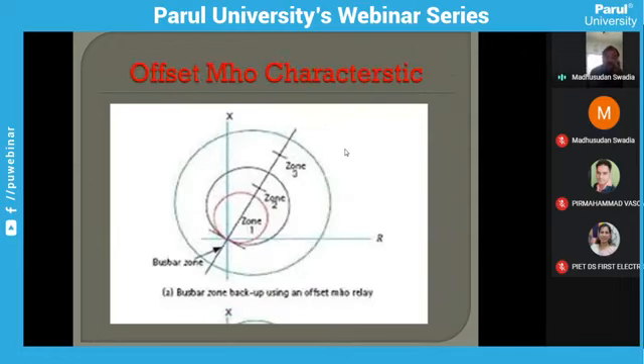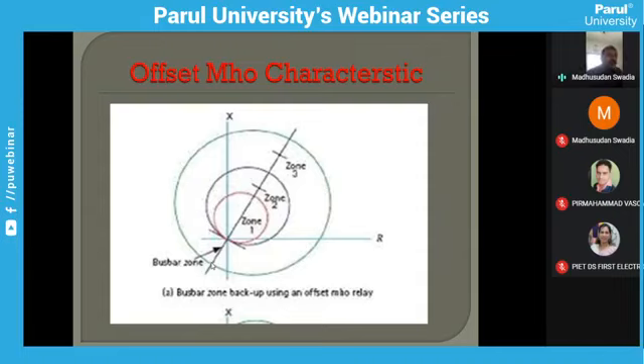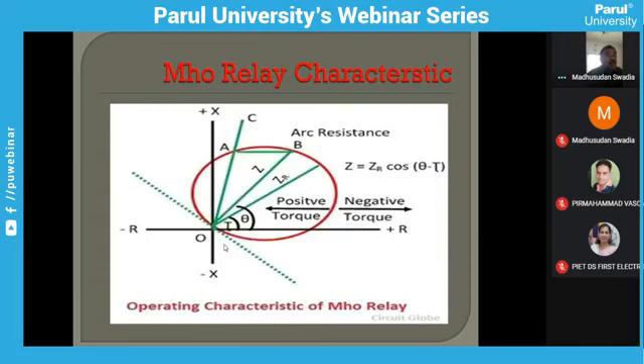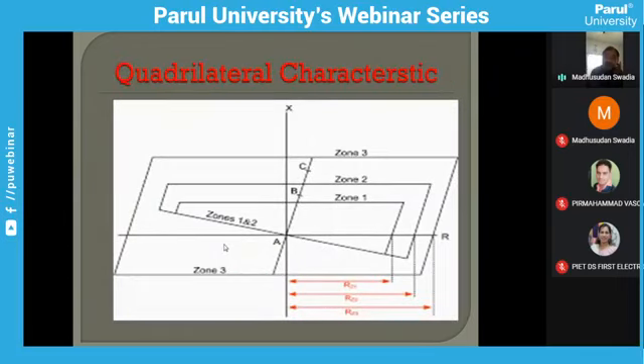The offset mho characteristic is a circle offset below the origin line. This is significant because it acts as backup to the busbar protection scheme — whenever a fault takes place on the rear side of the CT, it will operate after a time delay of 300 milliseconds or Zone 3 time. The quadrilateral characteristic is used nowadays in all numerical relays. Its major advantage is that it has a specific setting for both the reactance (X) and resistance (R) axis separately, which is especially useful when earth fault occurs with arc resistance.